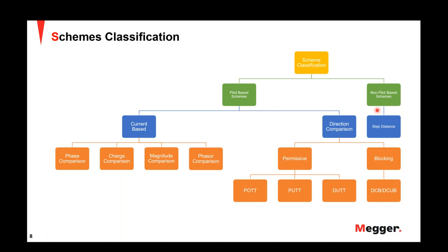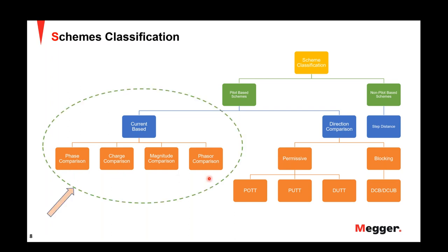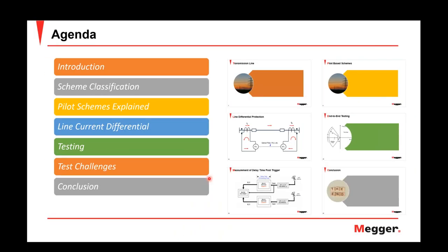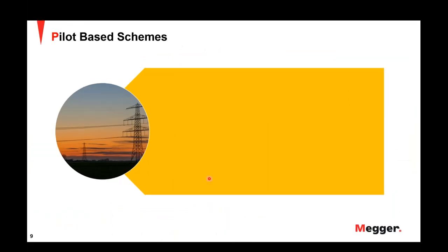Under the current-based schemes, you have different methods that the design engineers, really manufacturers, follow: phase comparison, charge comparison, magnitude comparison, and phasor comparison. So in today's webinar, our focus will be solely on the current-based schemes. Okay. I'll talk a little bit about pilot-based schemes.